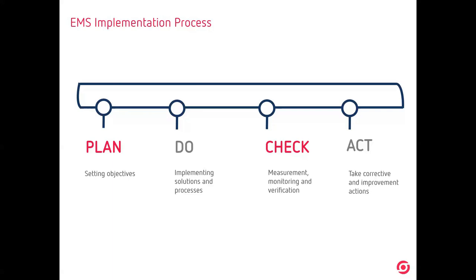Okay, there are installations where the consumption is very stable, so we can measure during 1 month, for example, because we know that all the month is the same consumption, and we have installations where the consumption fluctuates during the month, winter, summer season, etc. So maybe we need more time. Maybe we need 1 year of data. So it will depend on how we consume the energy. So this is why we also have to set the objective. The objective can be improving the energy efficiency after 1 year, because we need 1 year of collecting data. Once we do the corrective actions, we will start again, planning new things, doing, checking, and acting.